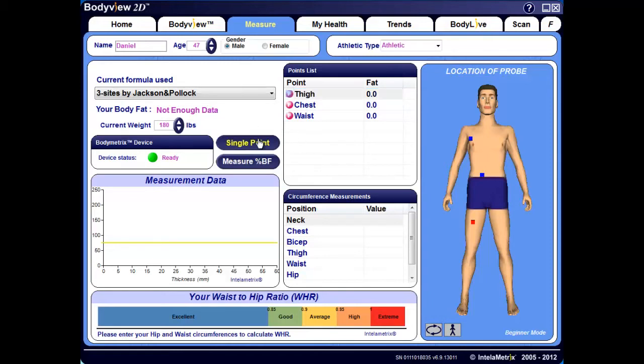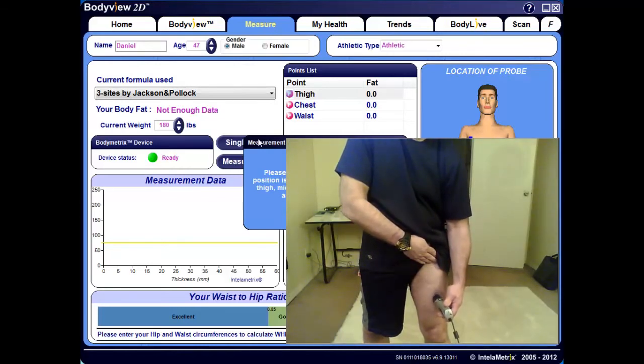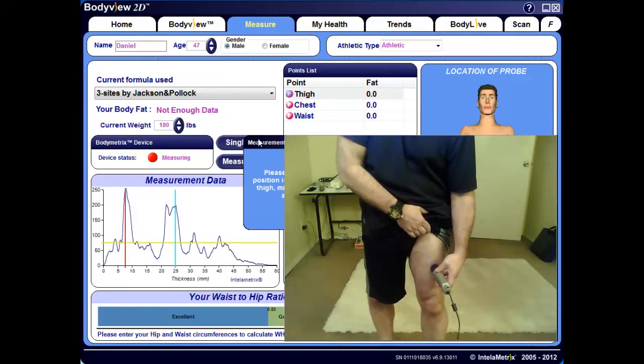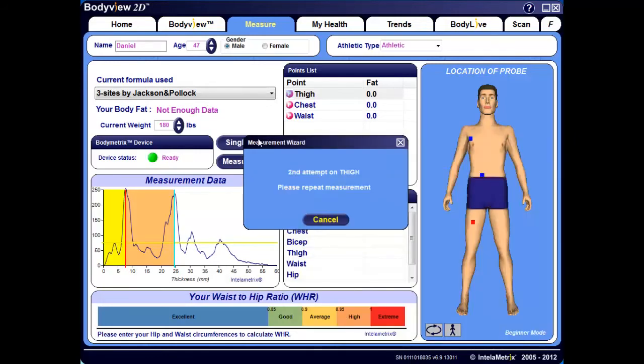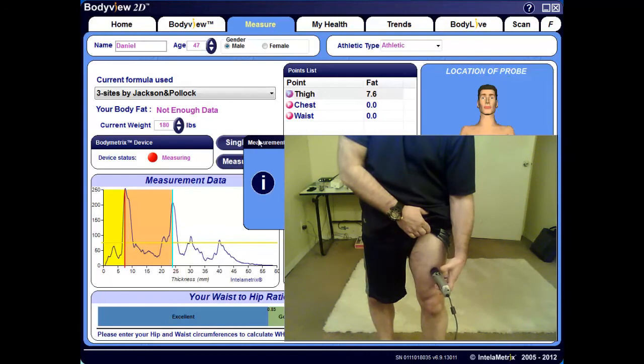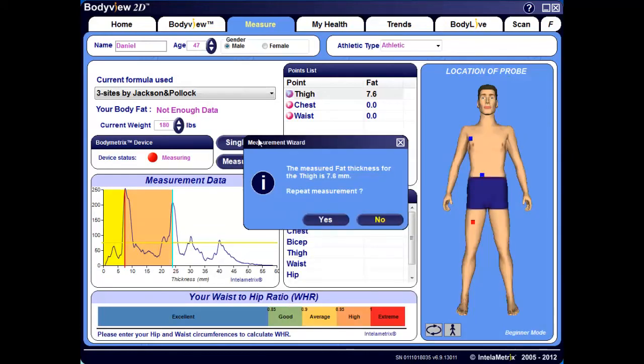After clicking on Single Point, place the device on the site point and without pressing the button, spread a thin layer of gel by moving the device up and down approximately one inch. When you're ready to make a measurement, press the button on the device and move the device up and down at a comfortable speed, making sure to stay within the one-inch area for three to four seconds, and then let go of the button. The Measurement Wizard dialog box will prompt you for a second measurement, so repeat the same process by pressing the button and moving it up and down for three to four seconds. You're moving the device about a quarter to a half inch on either side of the measurement point.